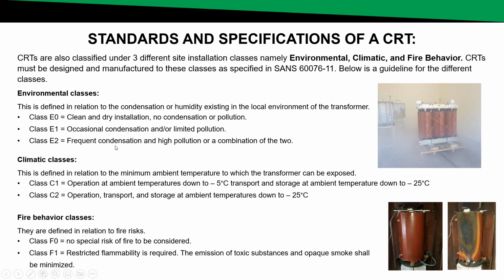Let's have a look quickly at the climatic classes. The climatic class is defined at which minimum ambient temperature the transformer can be exposed to. So class C1 is classified that the transformer can operate at temperatures not lower than -5 degrees Celsius. The transport and storage is allowed to be a minimum of -25 degrees Celsius. Class C2 means that the transformer can operate, be transported and stored at a minimum of -25 degrees Celsius.